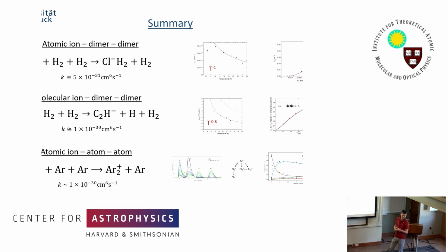Another maybe simple question. How do you actually do the temperature control? It's pretty basic. These cryostats only have an on and off, and when you turn it on, it does maximum cooling. We also have heaters, rods in the copper block for our trap, that we just put current through, and then it heats.